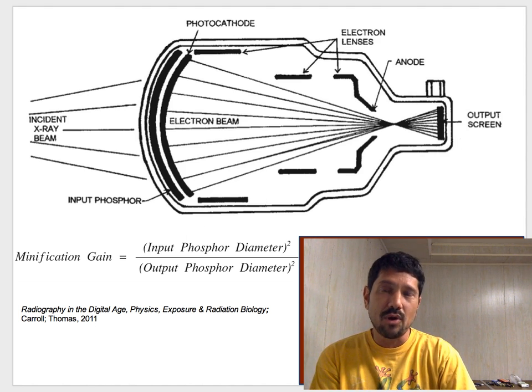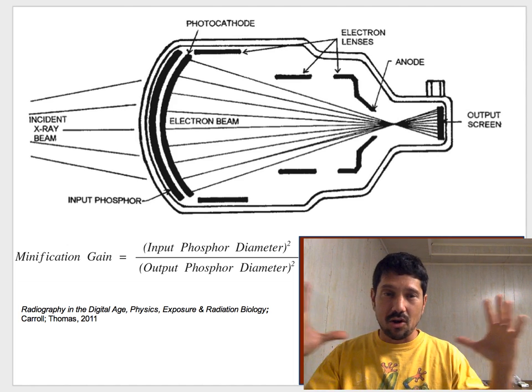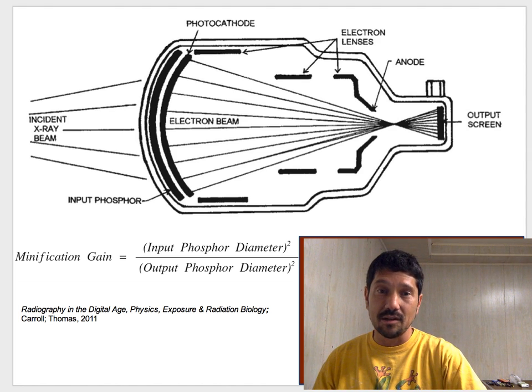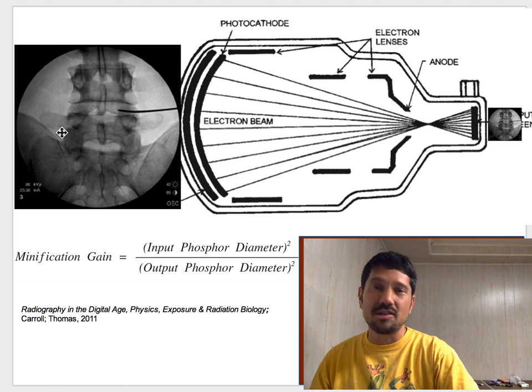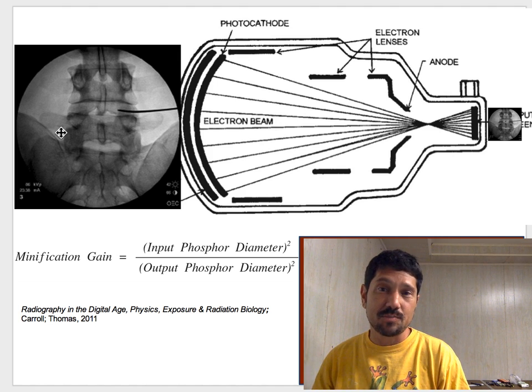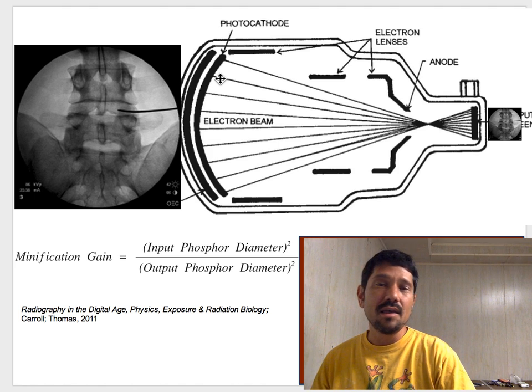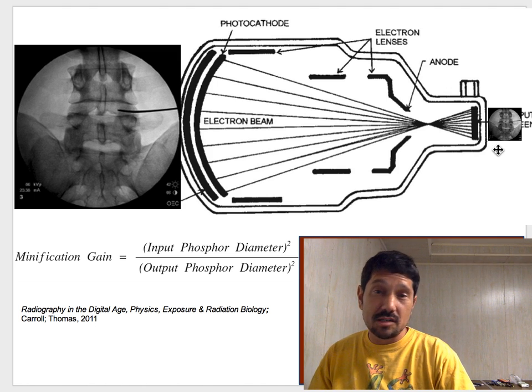So that is why we call it minification, and there's a brightness gain because you are taking a large image and making it small, and that's concentrating the signal. So you'll have perhaps a 4-inch real anatomy of someone's spine, or 3 inches, it'll be magnified up to maybe 9 inches by the time it hits your II. And then you are going to focus it down to your output screen, at which point it may be just 1-inch in diameter.